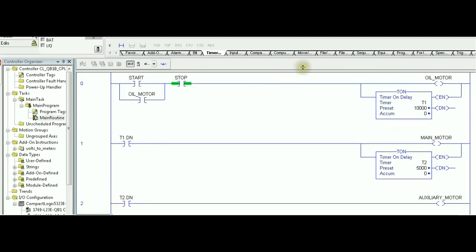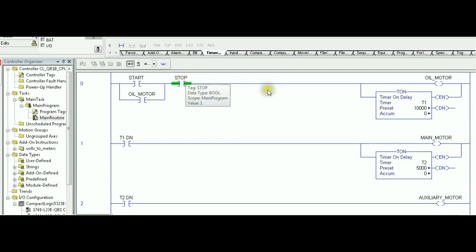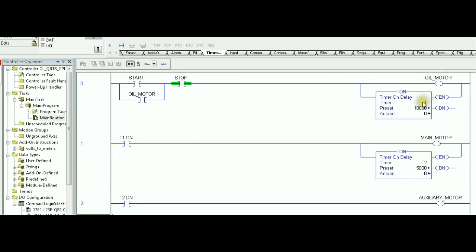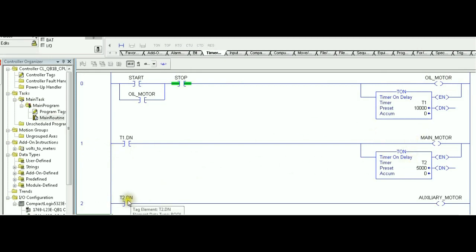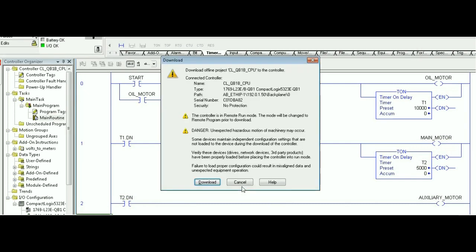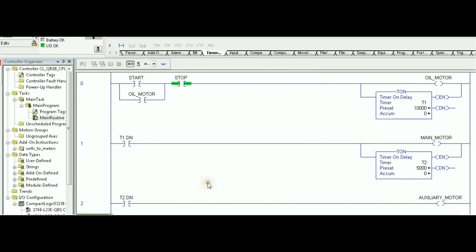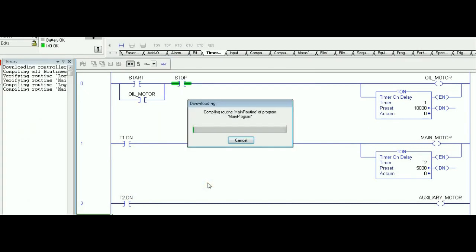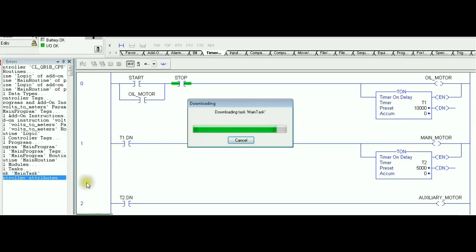So, that's our program right now. Start, stop are responsible to start and stop the oil motor and T1. After 10 seconds, both main motor and T2 is on. And after five seconds of main motor being on, the auxiliary will start. Let's download this program and see if this solution actually fulfills the requirement that we have to consider.